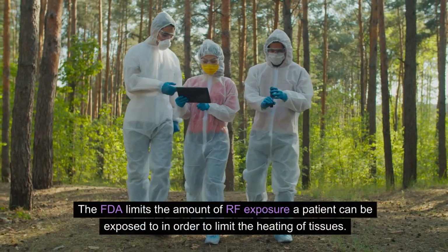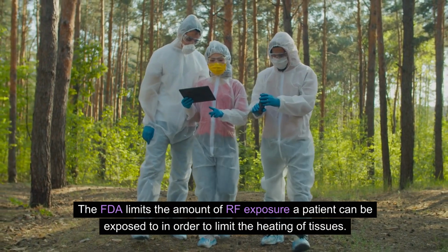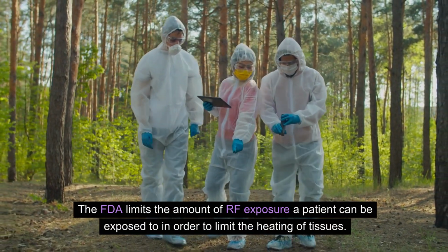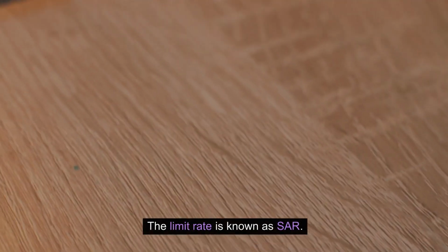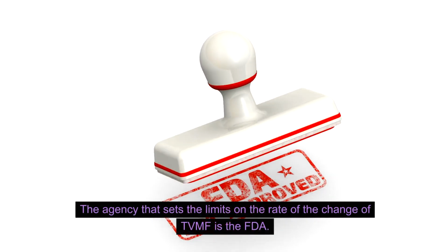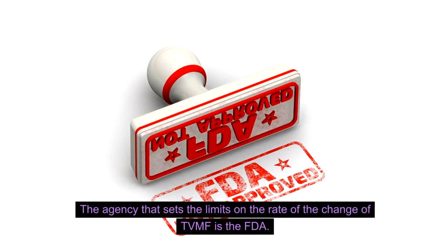The FDA limits the amount of RF exposure a patient can be exposed to in order to limit the heating of tissues. The limit rate is known as SAR. The agency that sets the limits on the rate of change of TVMF is the FDA.